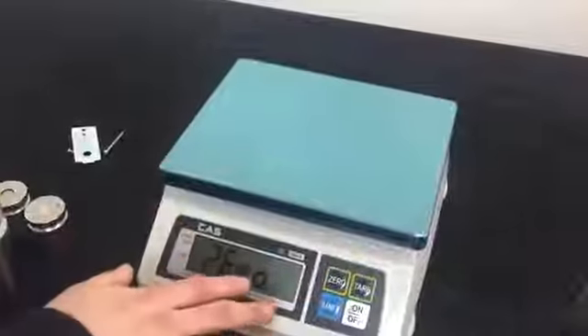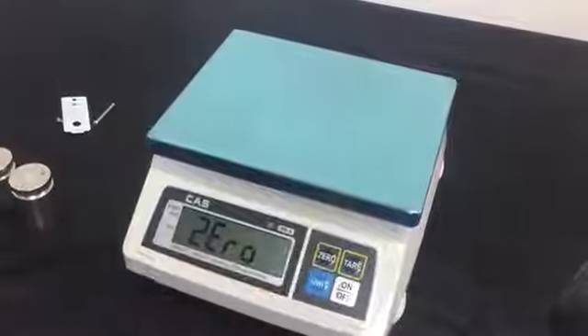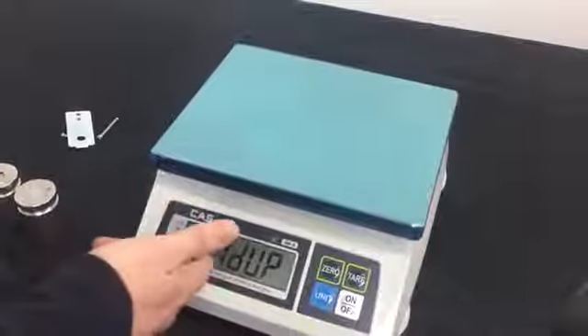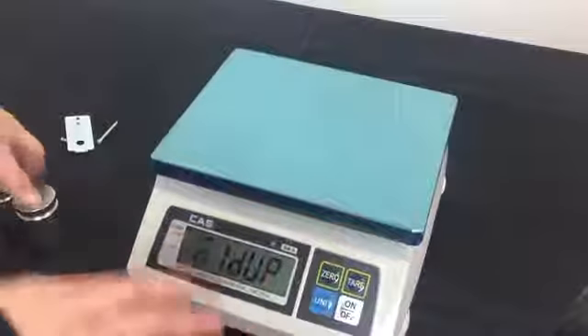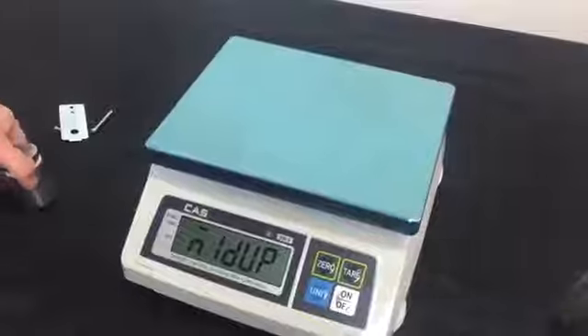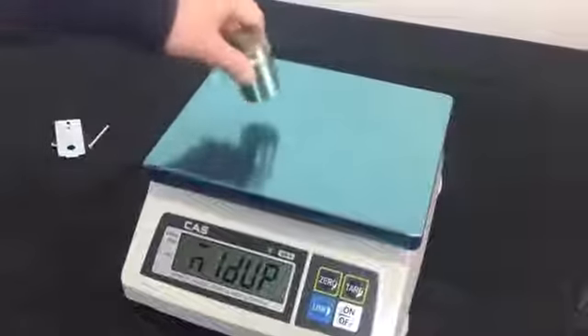0 is now showed on the display. This is your 0 calibration. So now make sure there's no weight on the platter. Just press the 0 key once. Once you press the 0 key, it'll show your raw counts. As you see, your raw counts are stable. It'll go to ND up. Now you put that middle weight that you just set up in the Cal 10, which is 2 pounds for our scale today. So I'm going to place 2 pounds on the platter.